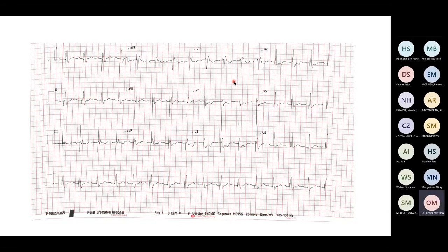And because they're capturing the conduction system directly, you get this very intrinsic, natural looking QRS that is resynchronizing the heart perfectly, really. This guy before we put a pacemaker in had a left bundle branch block with a QRS duration of about 190 something milliseconds. Screwed this lead in and pretty much instantaneously it corrects.